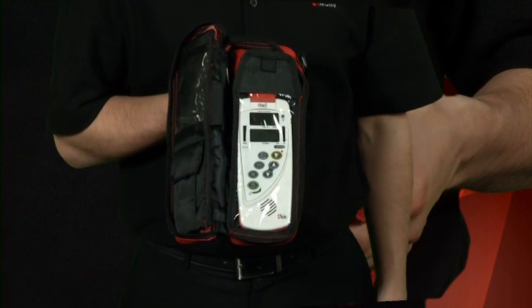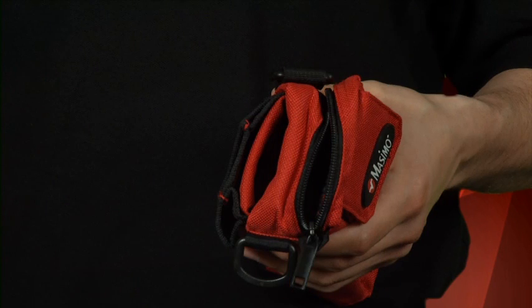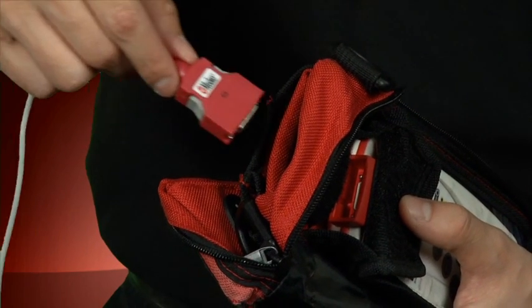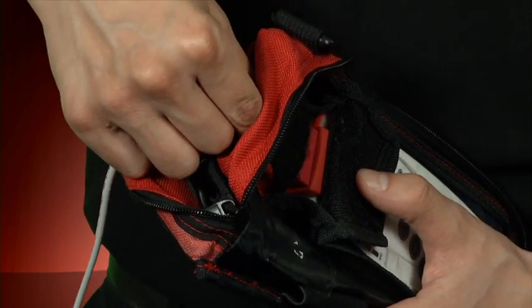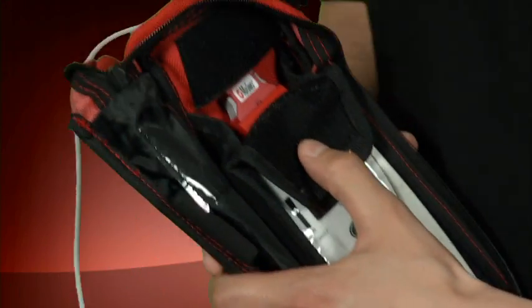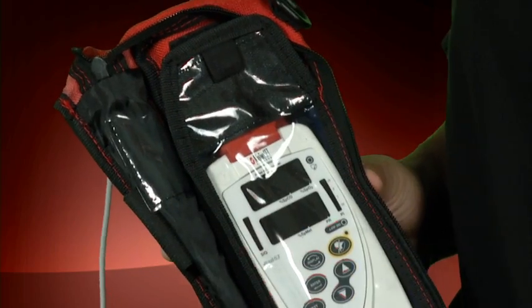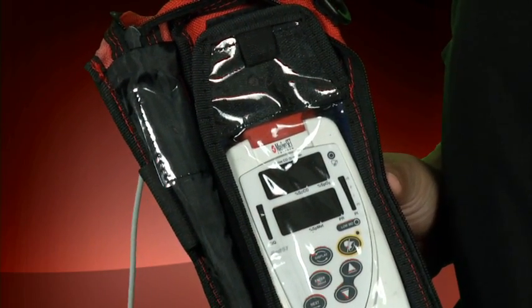Next, remove the sensor from the box. In order to provide the maximum protection to the cable, feed it through the Velcro at the top on the back of the case, not through the same opening that the Rad57 was placed in. Insert the connector into the Rad57 until you hear a snap. Make sure it's a firm connection and the cable is not twisted, sliced, or frayed.